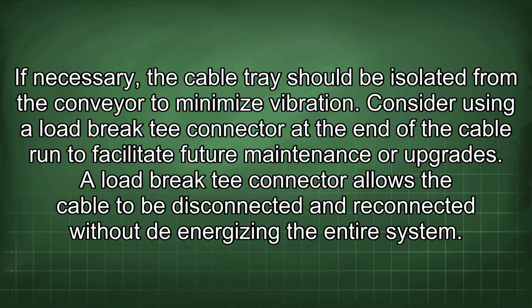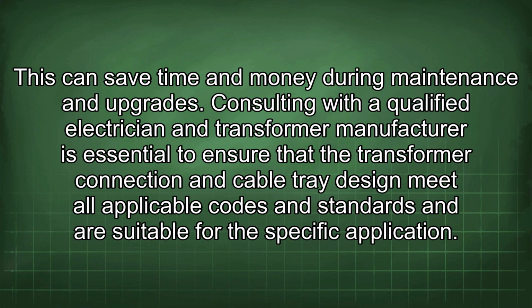Consider using a load break T-connector at the end of the cable run to facilitate future maintenance or upgrades. A load break T-connector allows the cable to be disconnected and reconnected without de-energizing the entire system. This can save time and money during maintenance and upgrades.